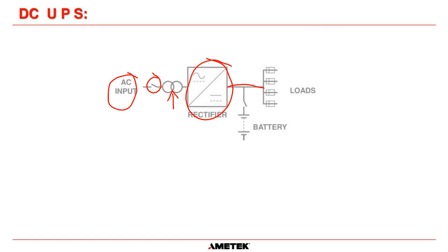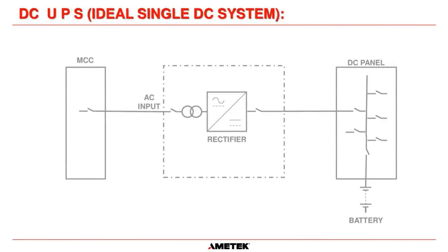And that DC bus splits off in two directions. Obviously, one is going to go down through a breaker to our battery down here. And then the other branch is going to take you to your load, your DC panel somewhere where you can send that out to your DC loads. So that is the most basic of single line drawings for a DC system.